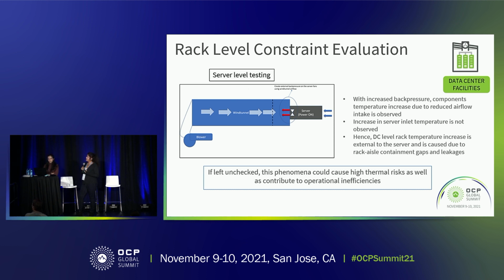So we ran a server level test where we stuck the server in a wind tunnel, and we created back pressure on the server fans. And we saw 2 observations. One of them is that the component temperatures on the server increased because obviously the fans are now drawing low amounts of airflow. The other observation is that we actually did not see any increase in inlet temperature in the server. So what that means is that this phenomenon is pretty much external to the system. It's not because of anything internal to the server. And the rack inlet temperature increase could be due to the rack aisle containment gaps and leakages.